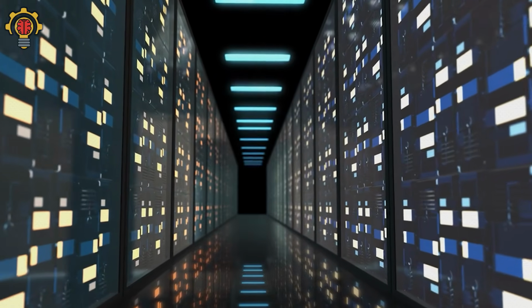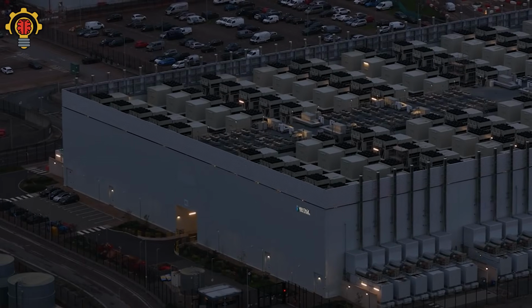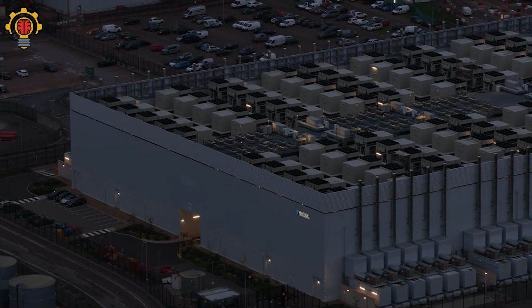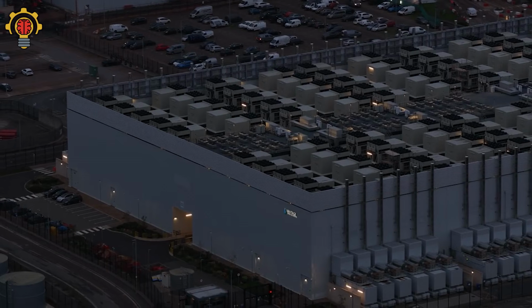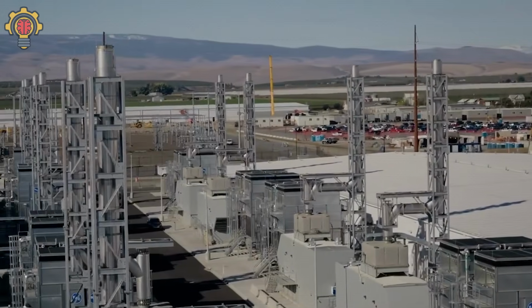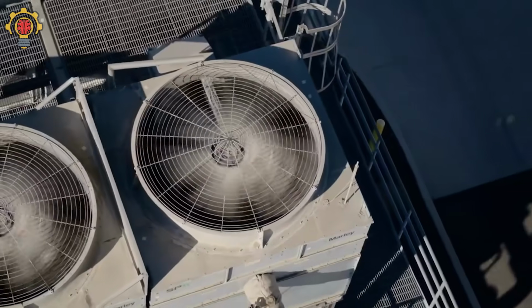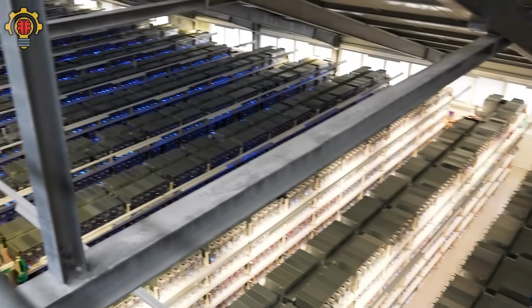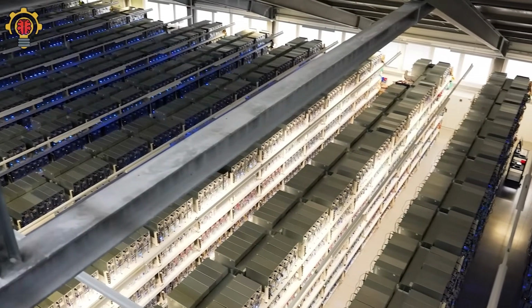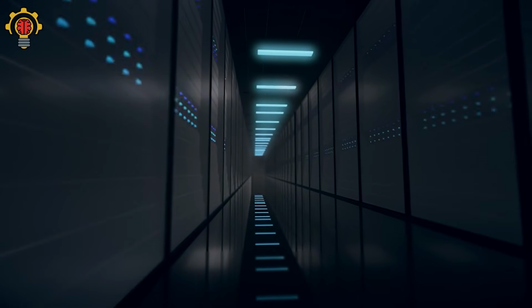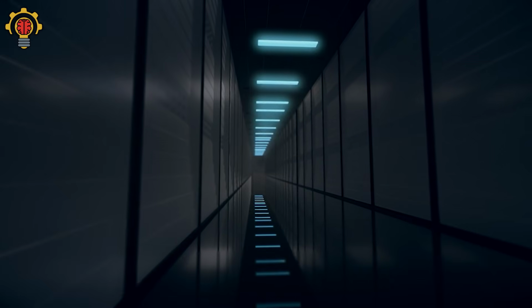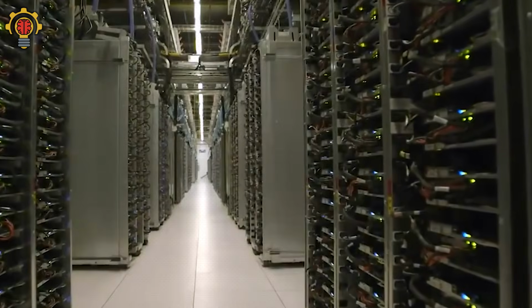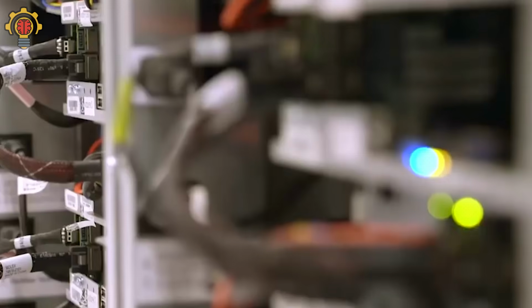Because unlike office buildings, data centers never sleep. They run 24/7, 365 days a year, day and night, weekends, holidays, even during storms and emergencies. That constant operation creates a non-stop heat load that must be removed continuously. If temperatures rise too high, servers can slow down, hardware can fail, and entire systems can crash.